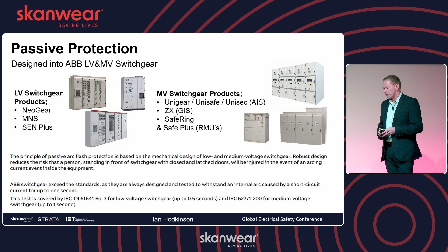All of those are designed and rigorously tested, so they have a robust design. They also have compartmentalized segments and chambers, separating areas so any arc can be contained. Another design point is that we normally vent, or design within the switchgear, a preferred path for exhaust gases from that energy and plasma if there's an internal arc, evacuating them through a chimney or flap and duct, out into a safe environment away from the operators. These are very important steps when selecting your switchgear, and also when we're designing and selling these products.